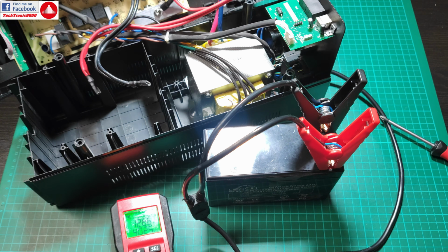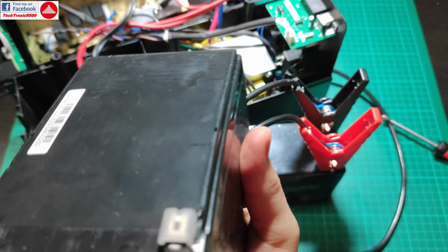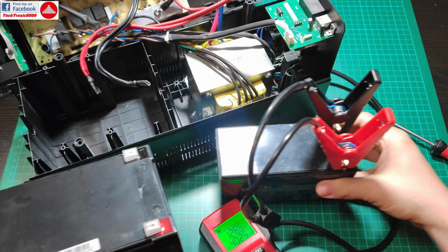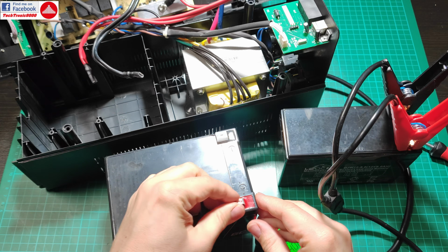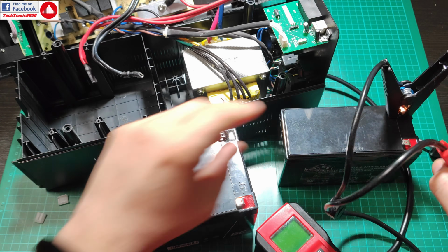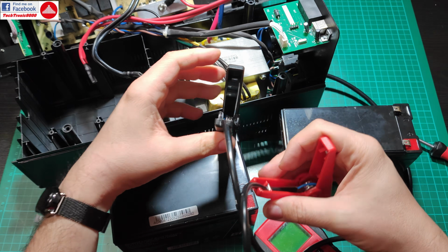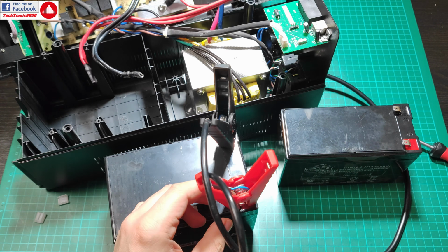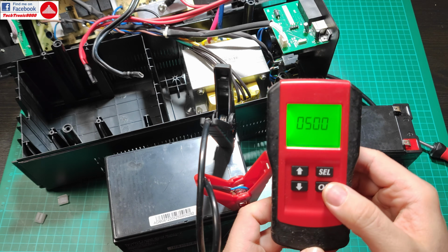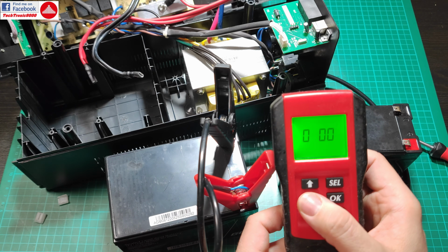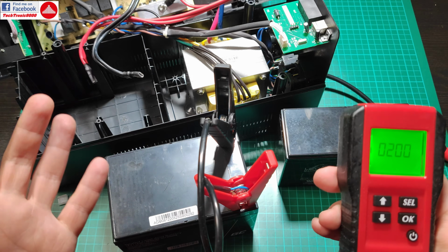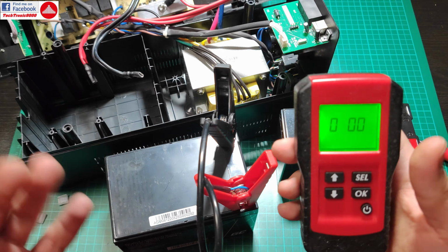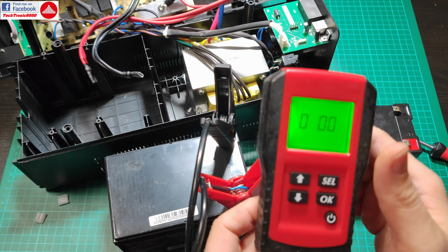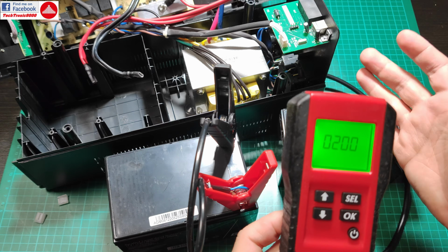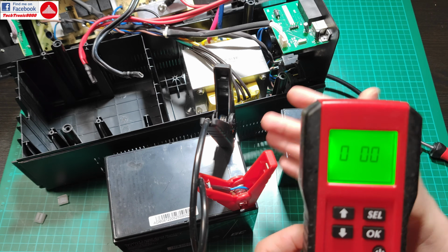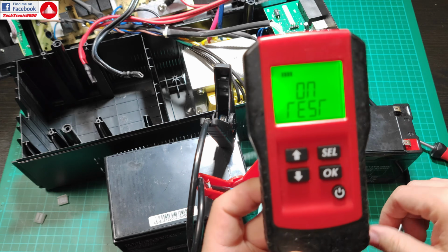In contrast, here I have the upgraded battery, the new one I'm going to place in, and I'm going to compare it with the old battery. I'll connect the clamps here, power this on, and use something like 200 amps as the setting, since this battery has a lot more potential being new and almost twice the size. If the old one should have around 100 and doesn't even reach 80, this one should be at least 200. Let's see if that's right.